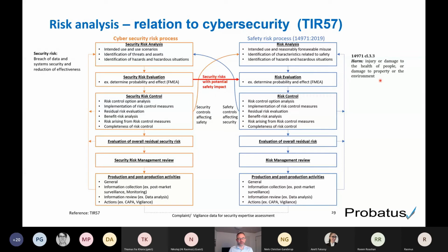That includes also harm to data, and this is different from the previous version of the standard, where it was physical injury that was stated. Now it could also be a breach of data or a reduction of effectiveness of a device that could be compromised through cybersecurity attacks, thereby causing a potential safety risk. So it's really important to be aware of this cycle, to go through it until we have mitigated to an acceptable level on both processes.